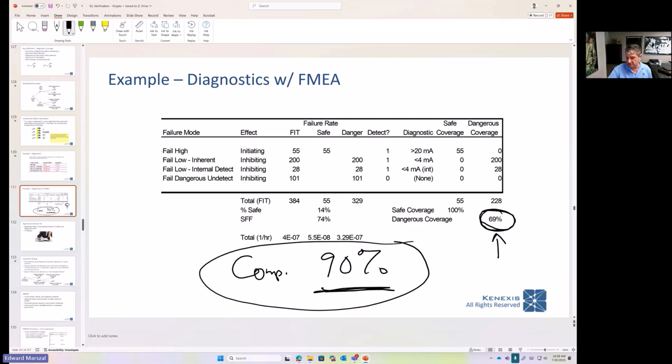So if that were the case, and now I need to bust out my calculator. Bring up my RPN 48 calculator here. So if I can detect 69%, that means that 31% of my failures were not detected. If I multiply 31% by 0.9, that's 27.9%. And then if I add my 69% back in, now I'm all the way up at 96.9% if I consider both.